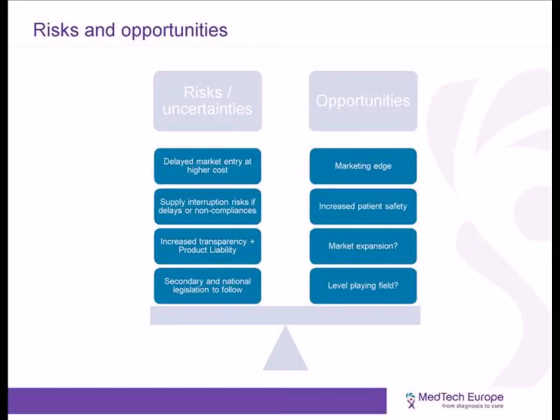And as for the increased product liability exposure, the MDR does require manufacturers to have sufficient financial coverage in respect of their potential liability. This requirement for financial coverage must be considered alongside not just today's CE marking obligations, but also alongside new rules in the MDR, like the requirement to make information public in Eudamed, the obligation to provide authorities with product technical information, or the obligation for authorized representatives to report termination of their mandates with non-compliant manufacturers. These new obligations mean that there is much greater potential for non-compliance to become common knowledge and for liability cases to therefore be more regularly raised by aggrieved third parties.